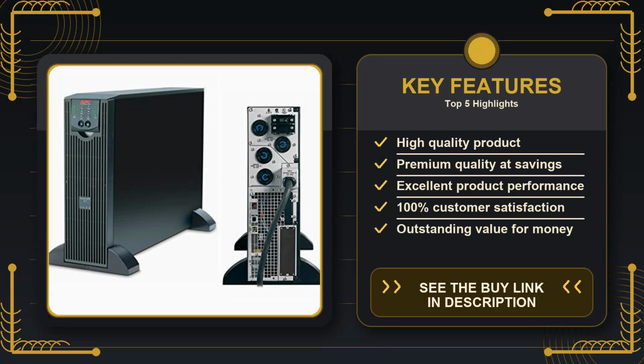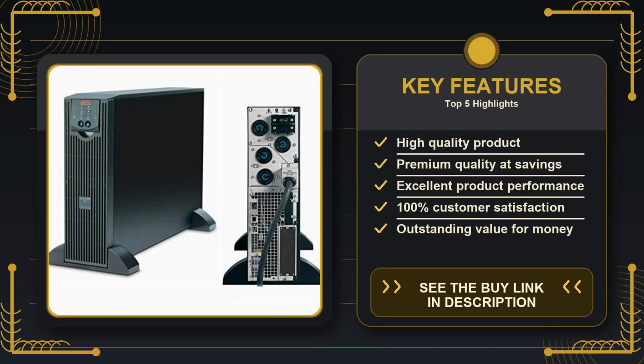What people most often worry about with any UPS is the runtime. How long will it keep things alive when the grid quits? With the RT series, the battery pack is sized to give you roughly 10 minutes of full load backup. In a real office, that looks like: you lose power, the UPS kicks in, your servers get a clean shutdown script, your workstations save any open files, and the building's generator, if you have one, has time to kick on. 10 minutes isn't a marathon, but it's precisely the window most IT admins design their shutdown procedures around, and it's far more useful than a UPS that can only hold the lights on for a minute or two.